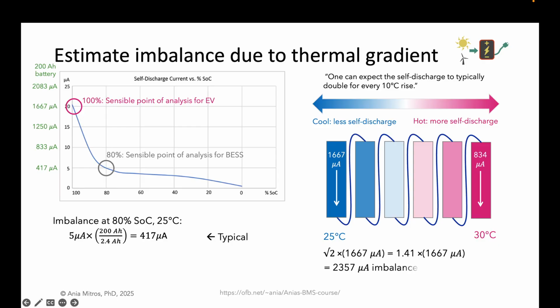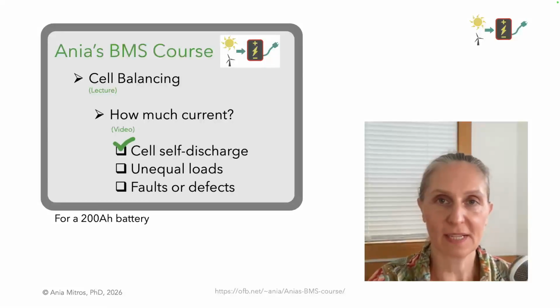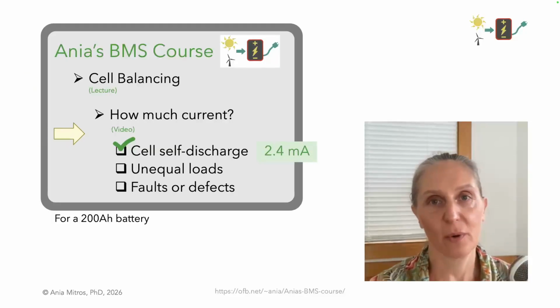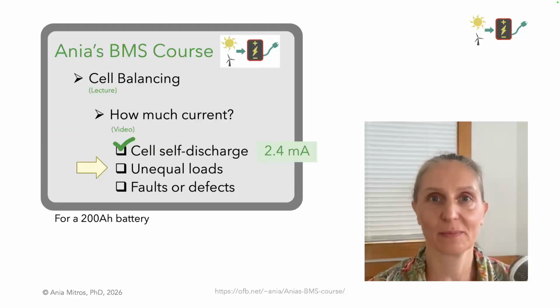Since self-discharge roughly doubles for every 10 degrees centigrade, for a 5C gradient, we'll see 1.4 times as much self-discharge on the warm end of the battery than the cool end. So that's our answer, 2.4 milliamp imbalance. For this 200 amp hour battery pack, which spends most of its time near room temperature and is expected to experience a 5C thermal gradient, we can expect the pack to imbalance itself at a rate of 2.4 milliamps. Let's remember that number. Next, we'll consider the impact of unequal loads.